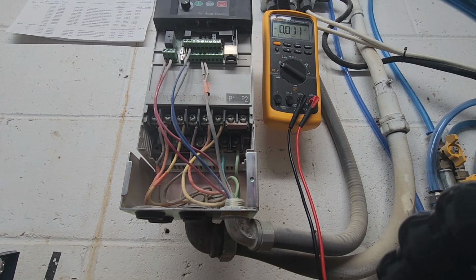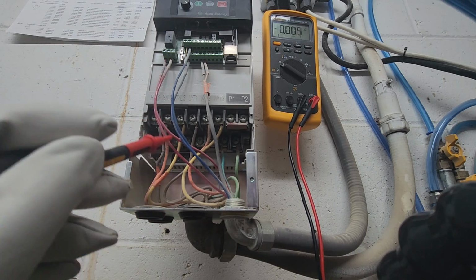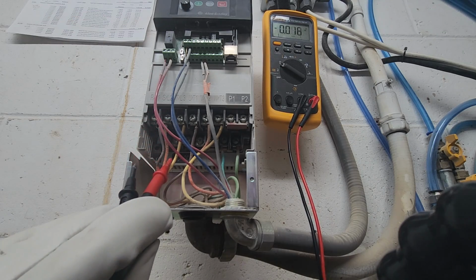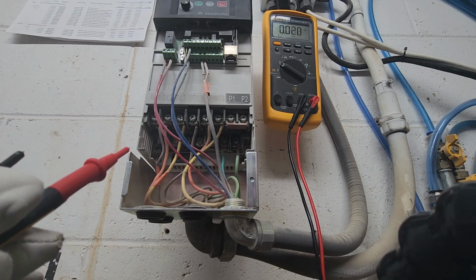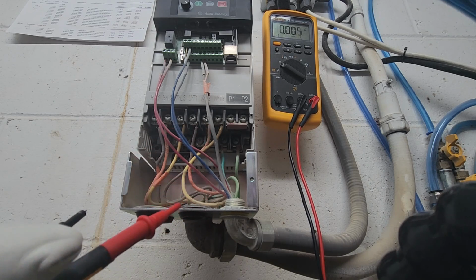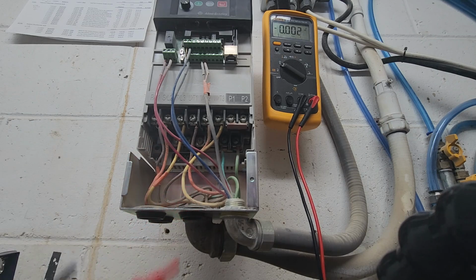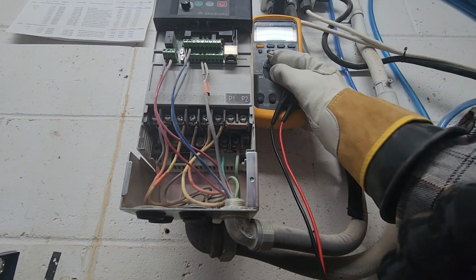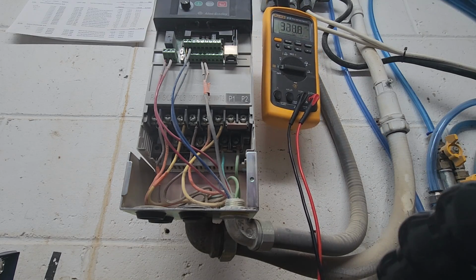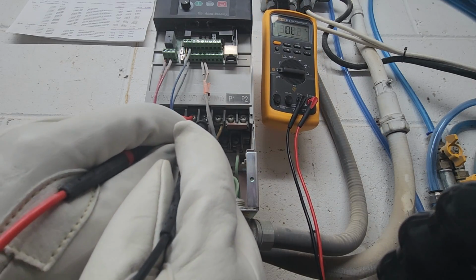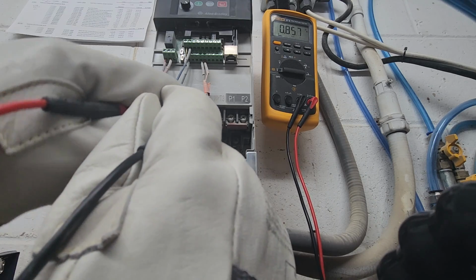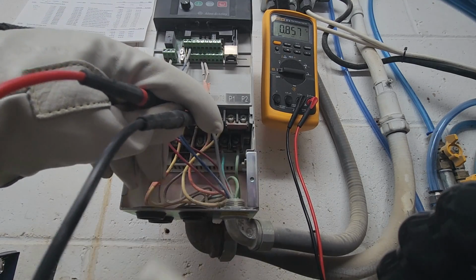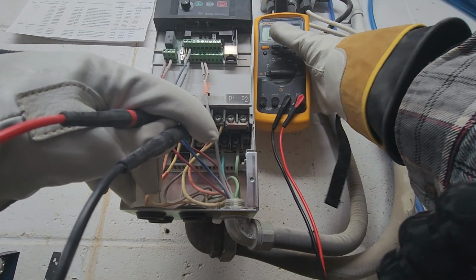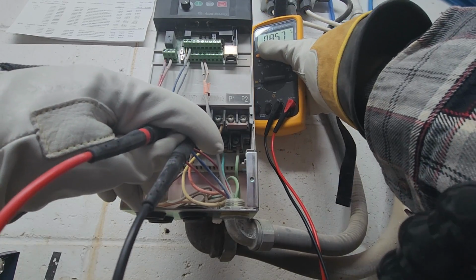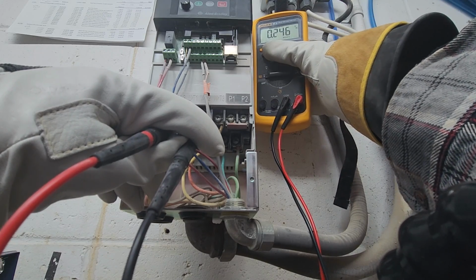One of the cool things you can do if you don't have access to your DC bus, it'll be labeled DC minus and DC positive. You can actually use just a regular multimeter that has a peak value, and what you'll do is you'll turn your meter into volts AC, and you have to do this with the VFD running, I would assume, let me see. Yeah, so you'd go terminal 1 to terminal 2 and then hit your min-max. On this meter you hit min-max and then you hit peak.